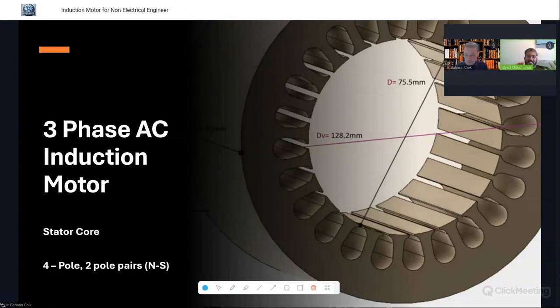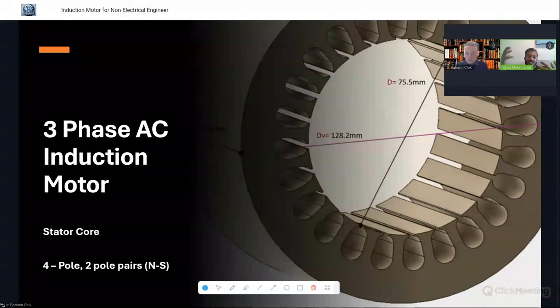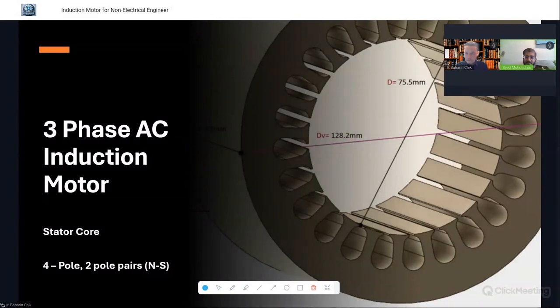This one is because a motor is usually the one that drives the pump. The question is for high viscosity fluid: is it better to use a high number of poles, or better to make some gearbox amendment at the rotating side to handle the high viscosity fluid, because it requires a high torque application, right? Basically, I think Shuib, you can answer that, right?